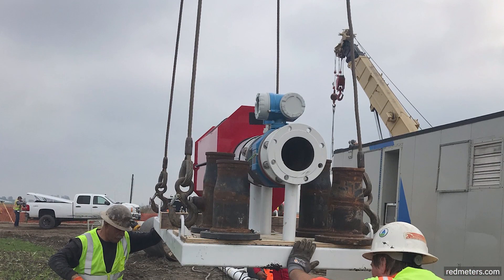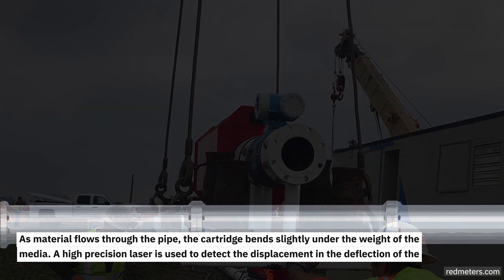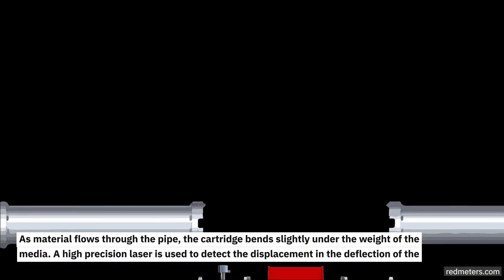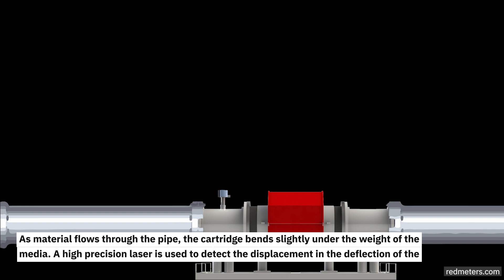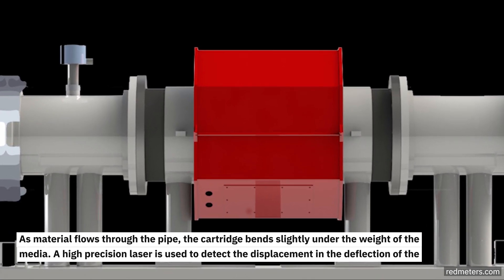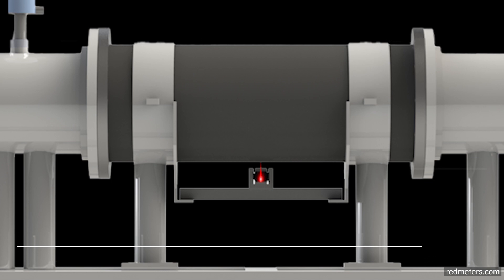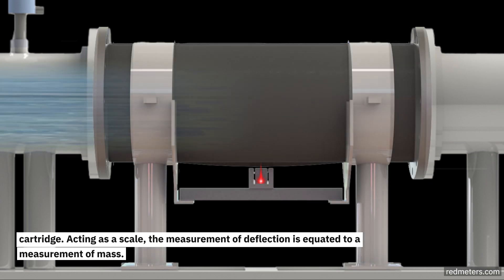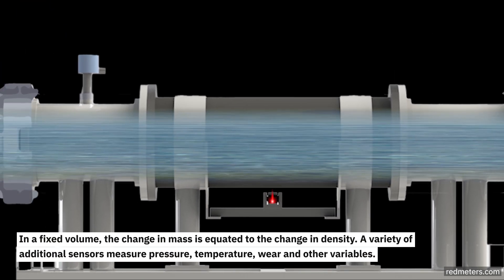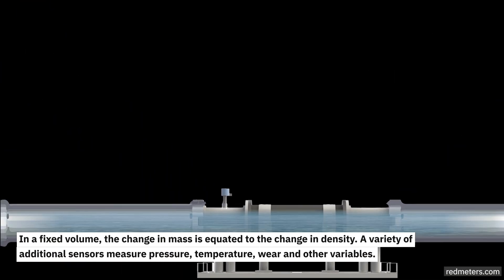As materials flow through the pipe, the cartridge bends slightly under the weight of the media. A high-precision laser is used to detect the displacement in the deflection of the cartridge. Acting as a scale, the measurement of deflection is equated to a measurement of mass in a fixed volume. The change in mass is equated to the change in density.